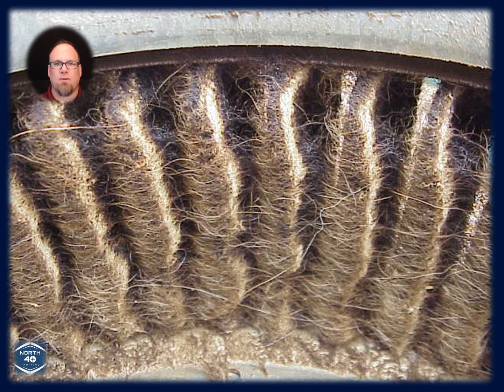Customer has an existing furnace. The old air conditioning system wasn't working properly, so the contractor sold them on replacing it and putting in a new air conditioning system. This was a condenser, a coil, line set, expansion valve, all of that. So they get the job done, and when the job is done, the new system is working very similar to what the old system was working like. And that was obviously a problem for the customer. They just got done spending a ton of money with the contractor, and the contractor was at a loss. So they replaced the expansion valve more than one time. And finally, they just wanted warranty on the whole thing, wanted their money back. They wanted to go with a different brand.